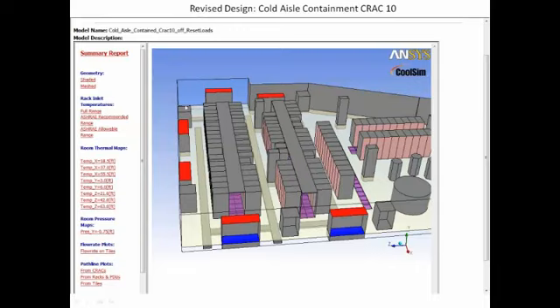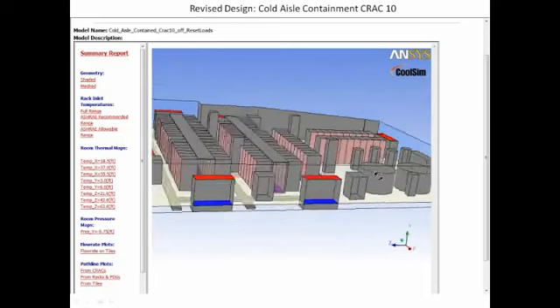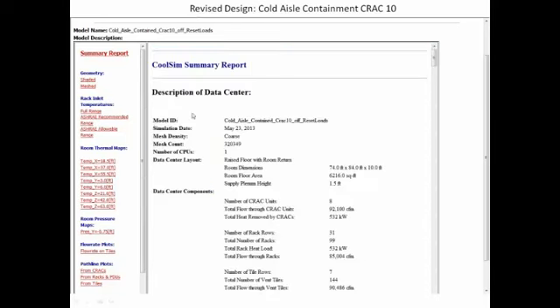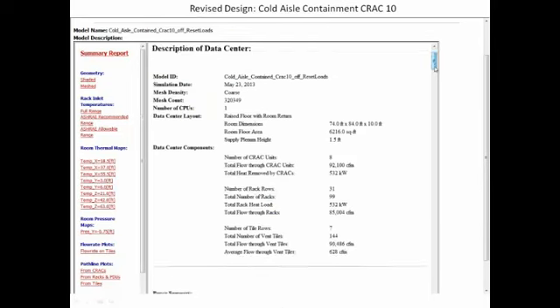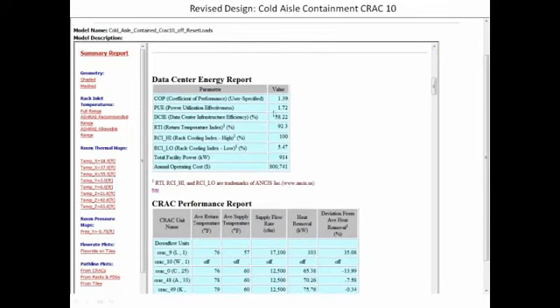So now let's take a look. What I did here is I shut that 30-ton off again over in this region. And I just wanted to see what would happen when we shut that 30-ton back off and went over here and had a look. And you see here my RTI is 92%. That's quite good. My RCI high, 100%. RCI low, 5%. So, you know, things aren't too bad here.